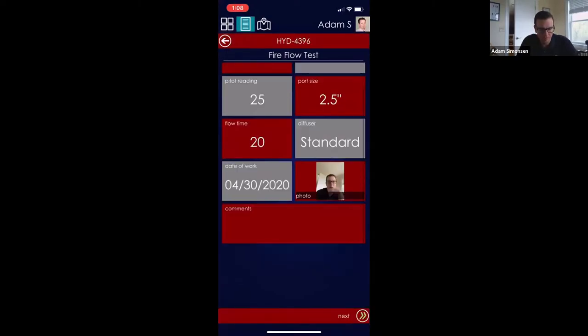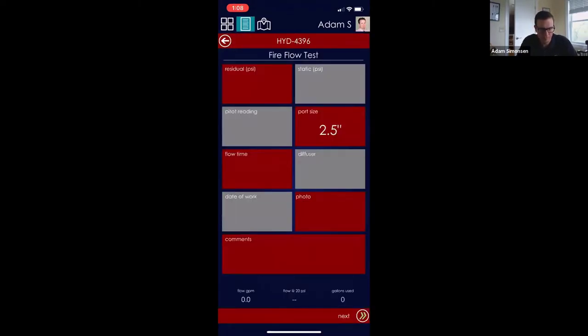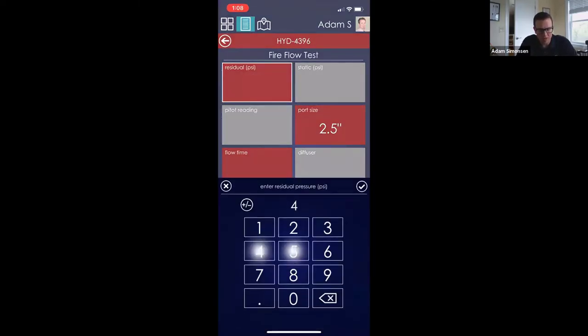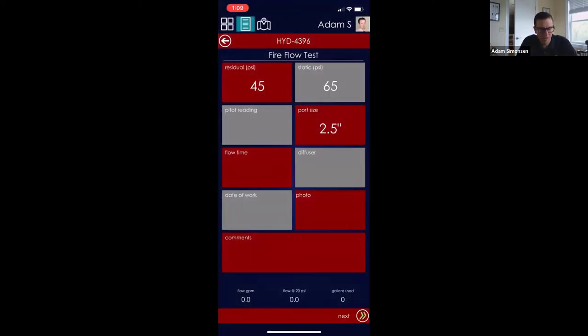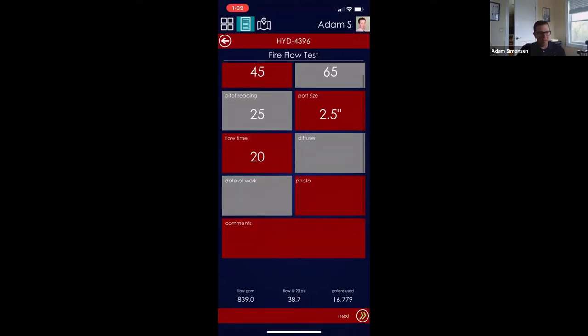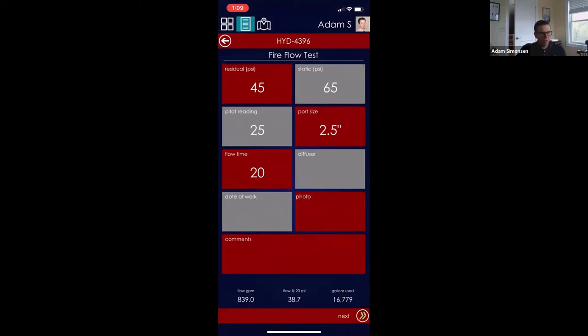One important thing to note is that calculations are built right into the form. When you fill out the values — static pressure, residual pressure, pitot reading, and flow time — it automatically calculates results for you. In this case, at the bottom of the screen it's calculating a flow rate of about 840 GPM and approximately 16,000–17,000 gallons used when you do this flow test.